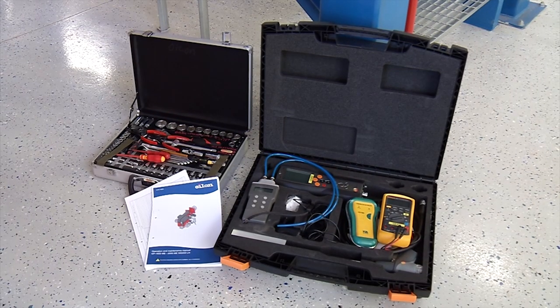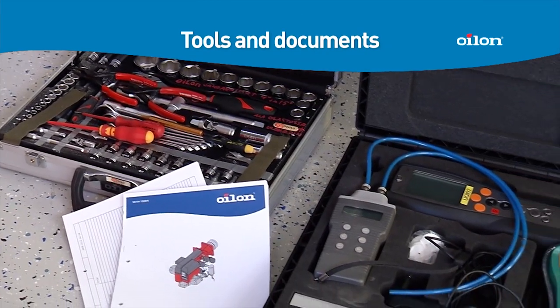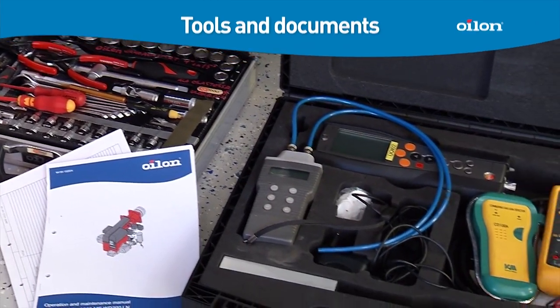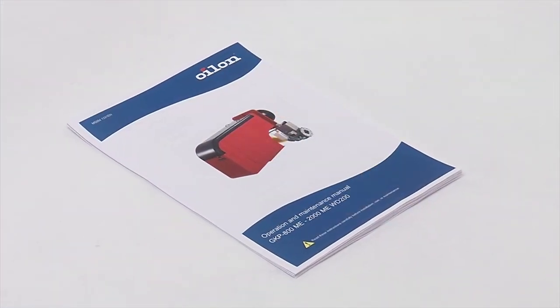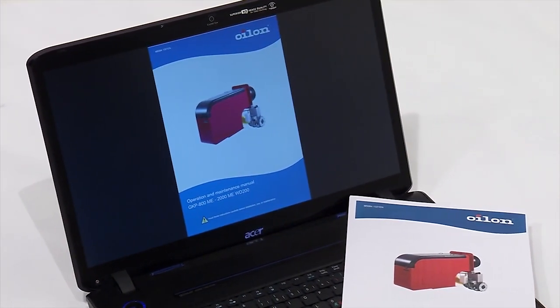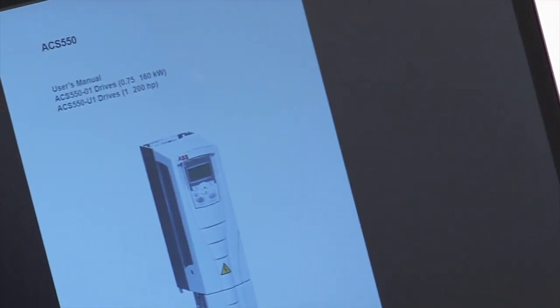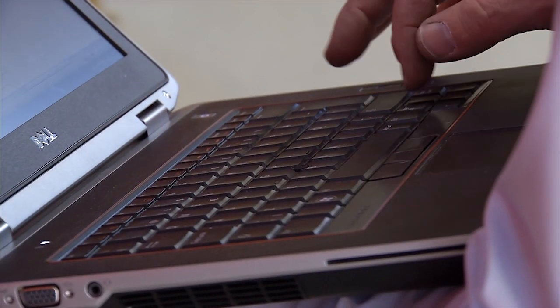Before you start commissioning or servicing the burner, check that you have all the necessary tools and documents. You will need the burner manual, either a paper copy or a soft copy on a laptop. Make sure you know the system password in case you need to log into the system. You will also need the frequency converter manual for setting parameters, and a laptop for storing and restoring system data.